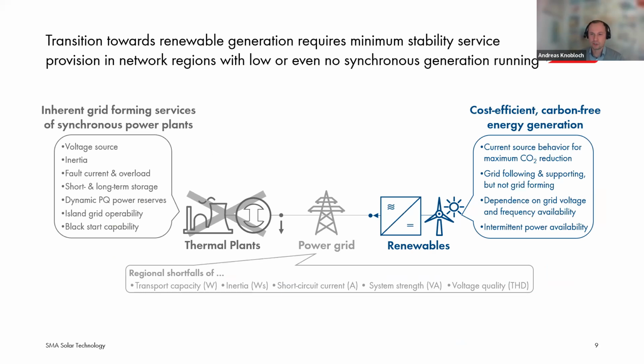And this transition towards renewable energy generation requires a minimum stability service provision in network regions with low or even no synchronous generation running. So we come from a power system which was centralized, where the conventional power plants with their synchronous generators had voltage source behavior, inertial behavior, fault current contribution, overload capabilities, short-term and long-term storage capabilities, dynamic active and reactive power reserves provision, island grid operability capabilities, and also the capability for grid restoration and black start. But these inherent grid forming services of synchronous power plants are becoming less, because the conventional power plants are phased out of the grids.